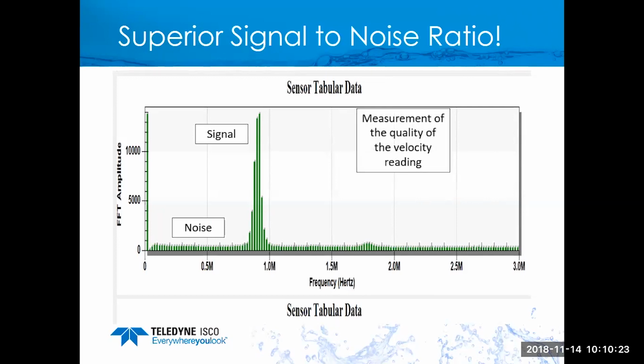This is known as a reading called Doppler power, which is really a measurement of the quality of the velocity reading. A couple of things make up this reading. One would be particles in the water. We typically need something to read, although in the case of the laser, the signal is so clean that we need minimal particles. But it's also related to the hydraulics. So this tells me at a quick glance that the hydraulics in this line are pretty good. I have plenty of stuff to reflect off of, and the laser likes what it sees. So all is well here.